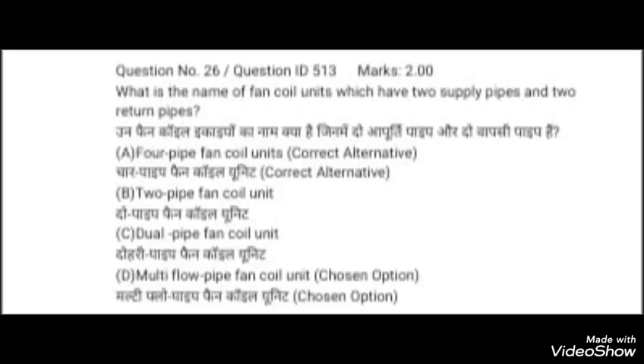What is the name of fan coil units which have two supply pipes and two return pipes? A. 4 pipe fan coil unit. B. 2 pipe fan coil unit. C. Dual pipe fan coil unit. D. Multi flow pipe fan coil unit.